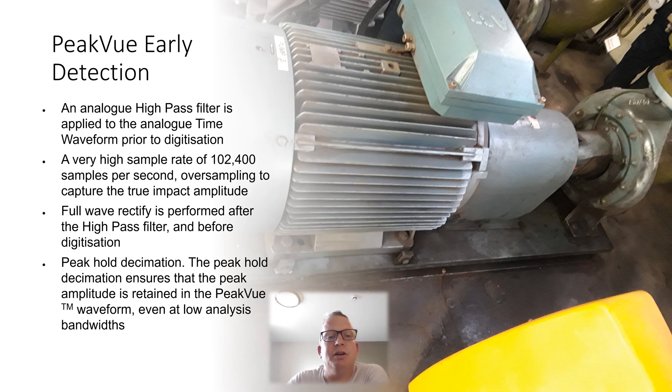Very basically we've got analog high-pass filter applied to the analog time waveform, prior to digitization. The bit which sets them apart is where it actually has a sample rate of 102,400. So the analyzer is sampling so fast that it's going to capture these very short transient minute shock pulses from the bearing. Very short pulse, short duration, really high frequency, they're sampling really fast to capture it. Then they rectify it, digitize it, peak hold decimation, which is where the name PeakVue comes from, where it holds a peak value and ensures the peak value is retained and it gives you some really crisp clear data.